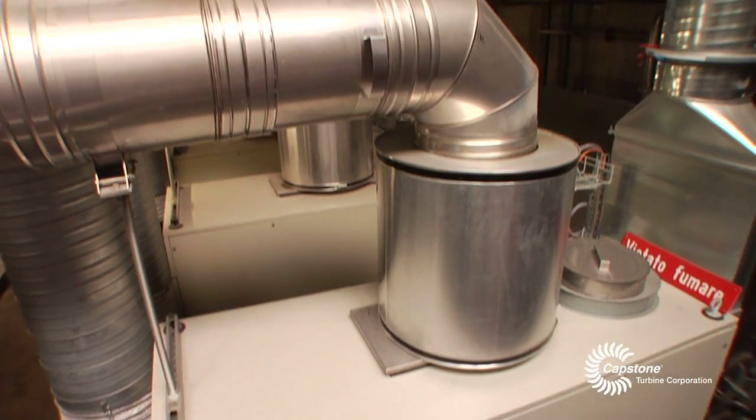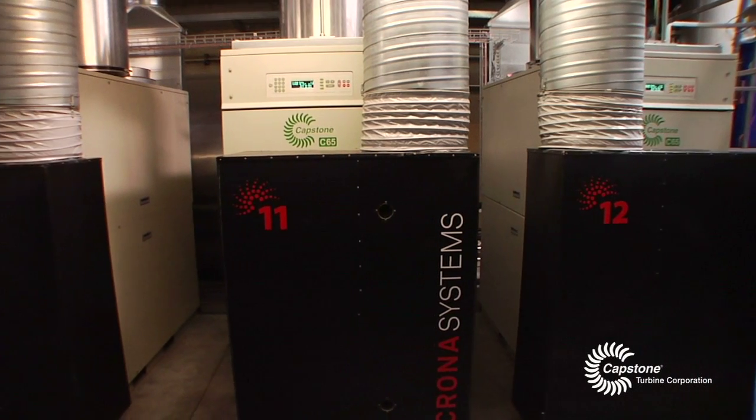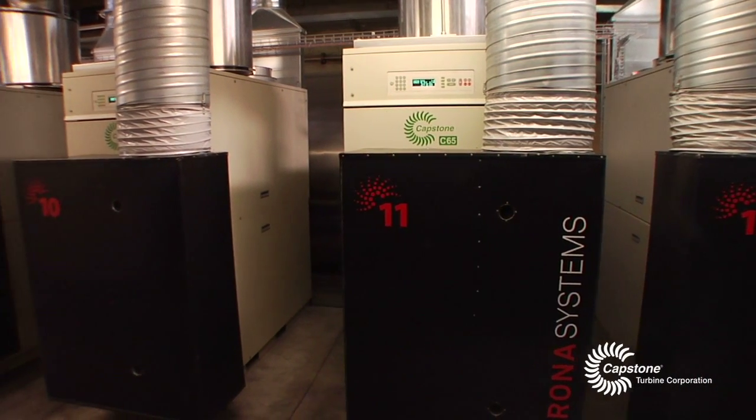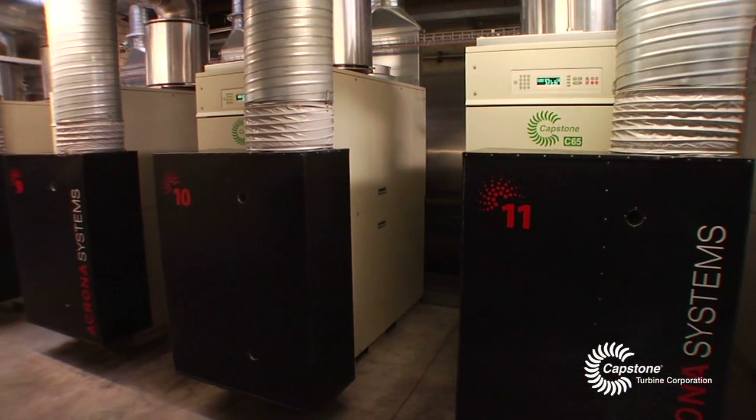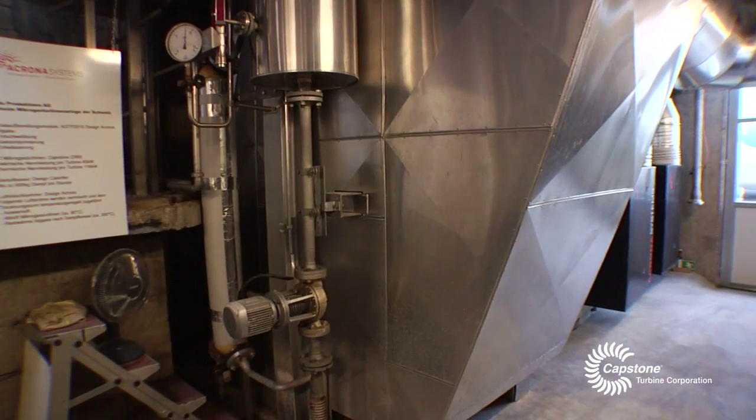The reason we have installed 12 C65 units is because of the exhaust gas temperature. The C65 comes with an exhaust gas temperature of 305 degrees Celsius, and this hot exhaust air is used for the direct production of steam.